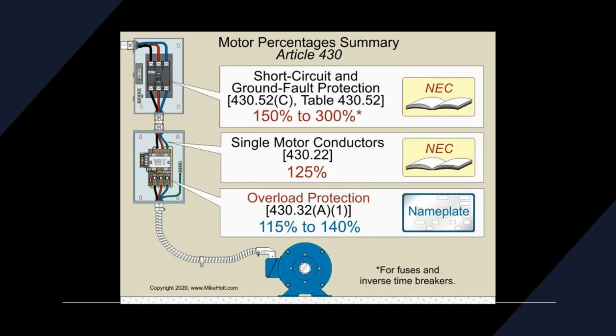Motor conductors from the NEC. Overload protection from the nameplate value. Okay? So this slide is incredibly valuable for that alone. If they're asking for FLC, it's going to see C for codebook. That's going to be short circuit ground fault. Motors is going to be out of motor conductors is going to be out of the code book, and overload protection out of the nameplate.